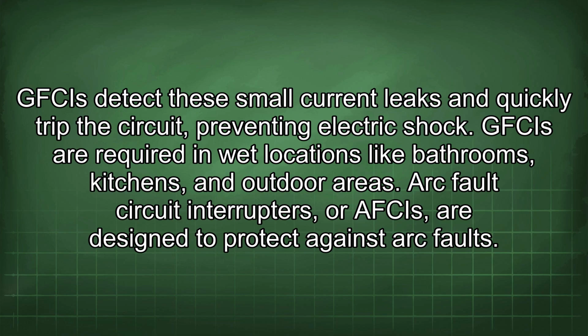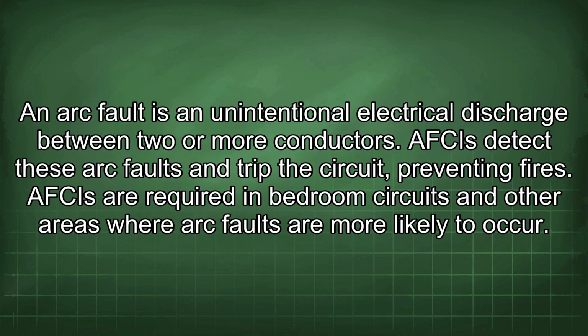Arc fault circuit interrupters, or AFCIs, are designed to protect against arc faults. An arc fault is an unintentional electrical discharge between two or more conductors. AFCIs detect these arc faults and trip the circuit, preventing fires. AFCIs are required in bedroom circuits and other areas where arc faults are more likely to occur.